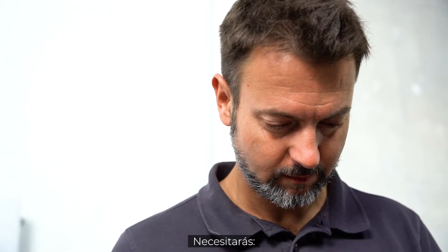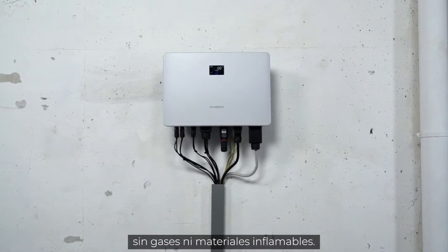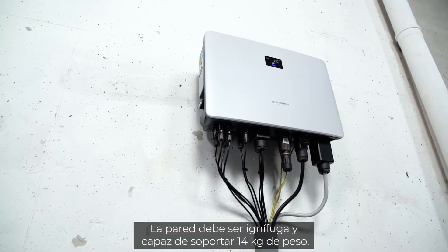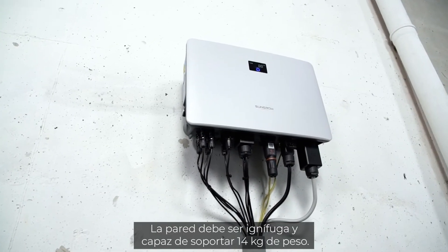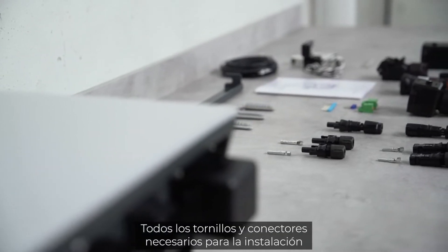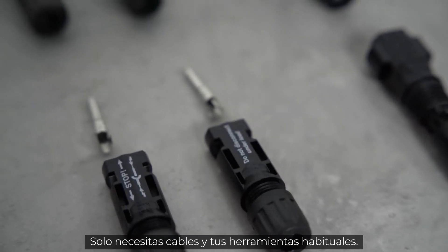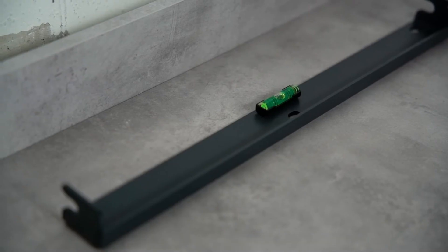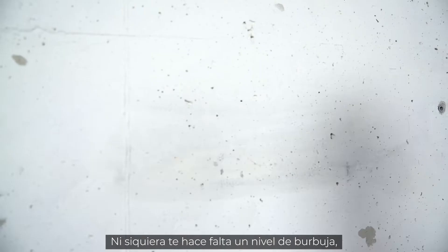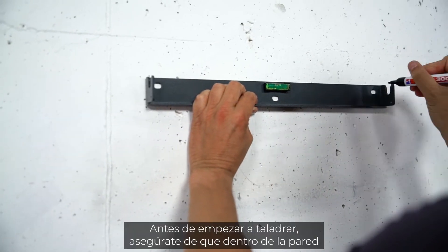You need a suitable place for the inverter. This means a room where no flammable materials or gases are stored. The wall must be fireproof and able to bear the weight of 14 kilograms. All screws and plugs required for the installation are already included in the delivery — you only need your own tools and cables. Luckily, you don't need a spirit level; Sungrow has it integrated in the mounting plate.